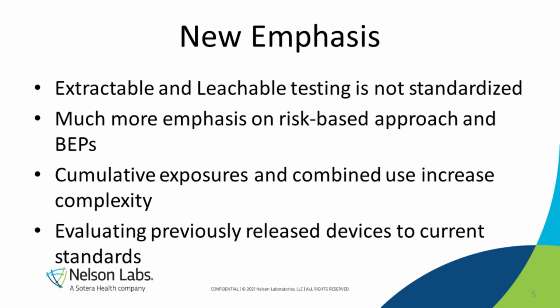So as you can see, that's the other change: we got rid of the X's on everything else and put evaluate. So that's the concept. You gather material and chemical information, you look at the risk of your medical device, and then based on the information you have about the materials, the processes they go through, and the risk of the device, you evaluate the endpoints of every other needed test category. So that's the concept of the new 10993-1. New emphasis on a risk-based approach, increased emphasis on extractables and leachables testing, and that's that chemistry information I was talking about, at least a portion of what could be chemical information.